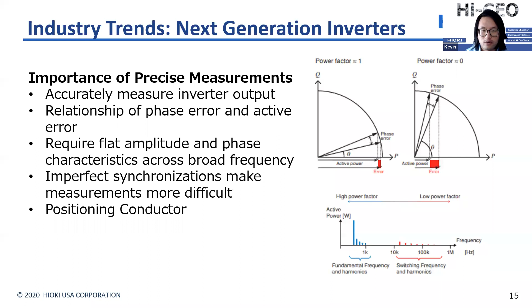So we were talking about the higher frequencies introducing a greater phase error. Current sensors typically will exhibit this gradually increasing phase error in the higher frequency region, simply because of the characteristics of the sensor's magnetic core and the circuitry. Also, different sensors will have different amounts of error. The through type eliminates any breaks in your magnetic core, which makes it easier to obtain uniform characteristics around the entire circumference of your core, and this allows for extremely precise sensors. This design, though, makes it difficult to disconnect your cables.